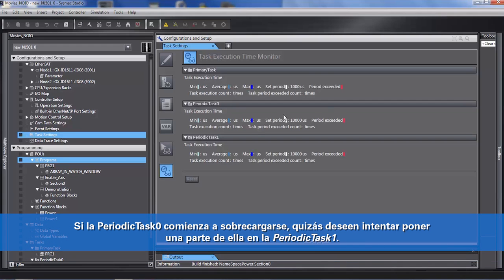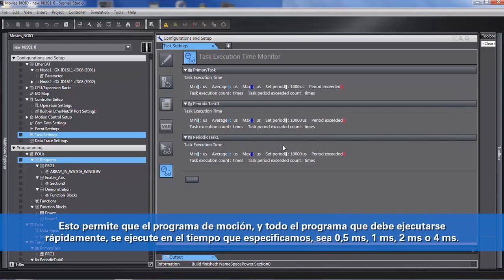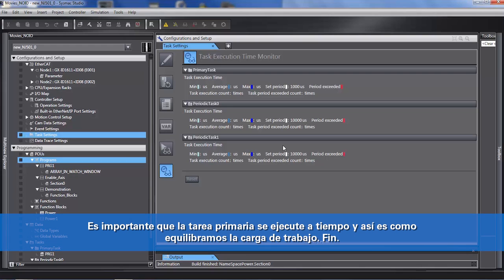If periodic task 0 starts to overload, they may wish to try putting some of it in periodic task 1. This allows the motion code and all the code that has to execute quickly to execute in the specified time — be it half a millisecond, one millisecond, two milliseconds, or four milliseconds. It is important that the primary task executes on time, and this is how we balance the workload.